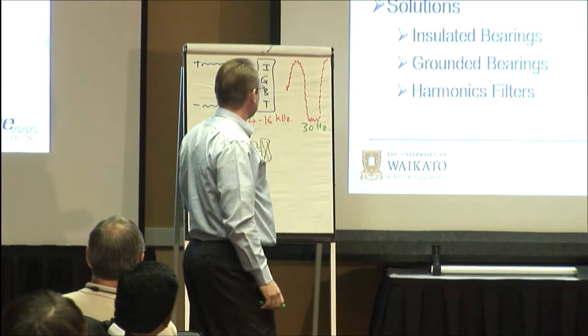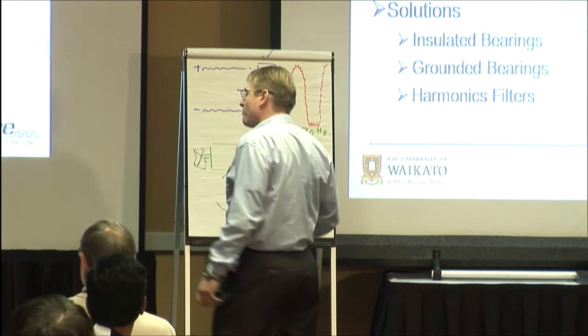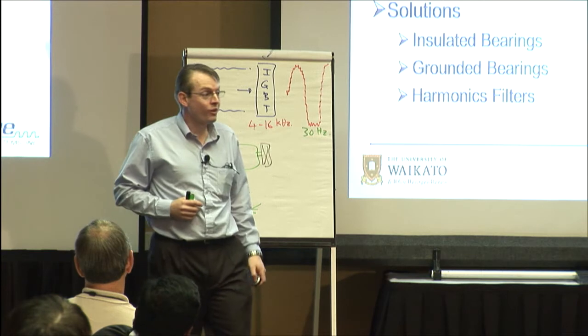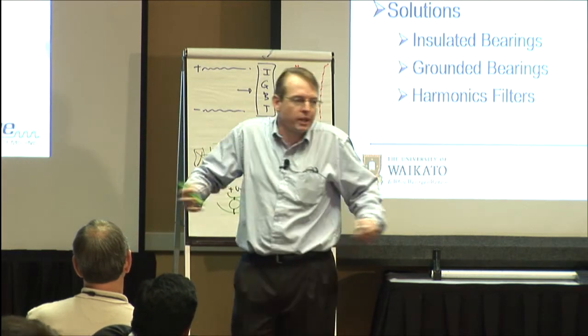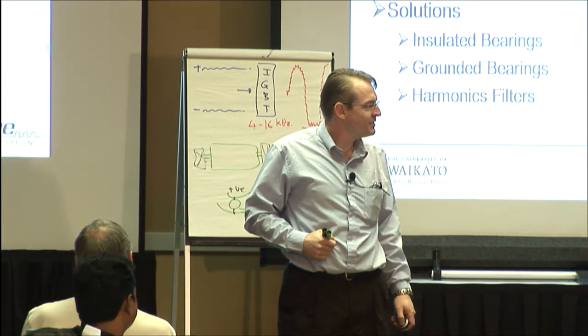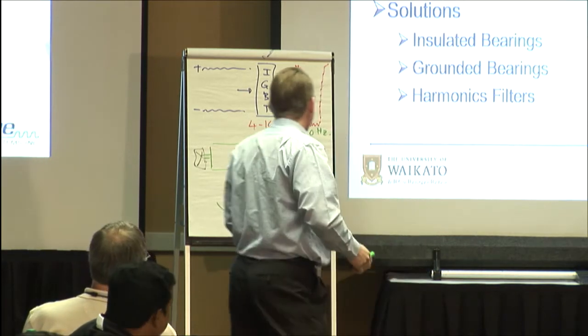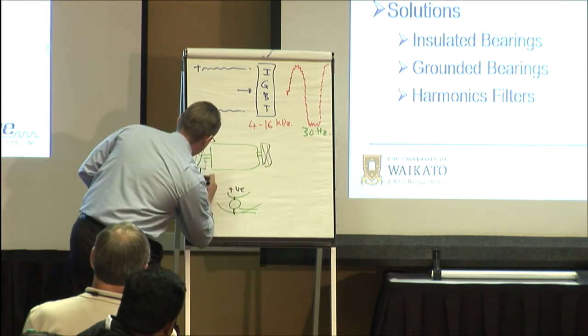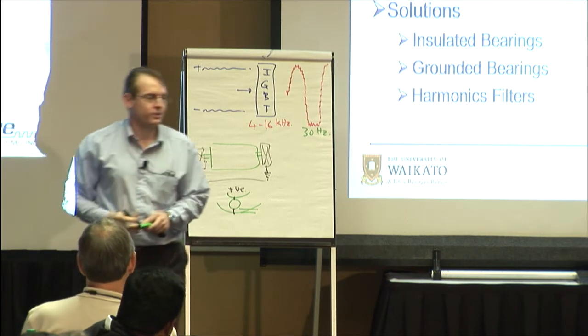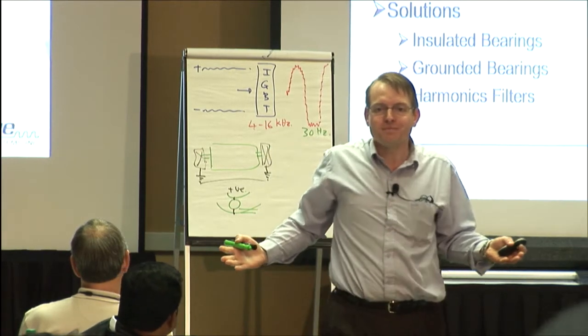So we're going to use grounded bearings, are we? Do we ground both bearings? What if we insulated the bearings? How about we insulate the bearings? It's still going to be looking for a path to ground, right? What happens if we ground both bearings? You've just created a loop, right?